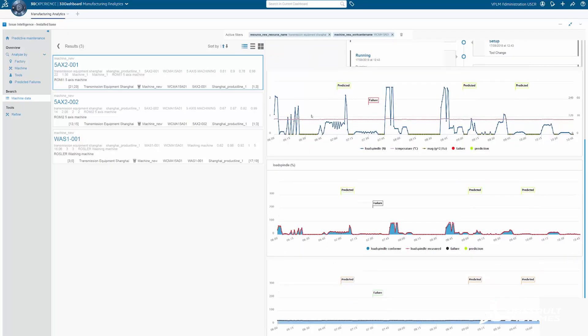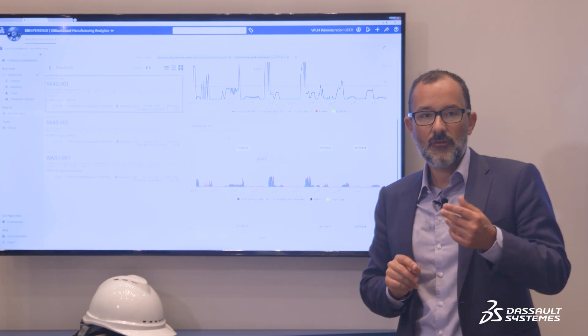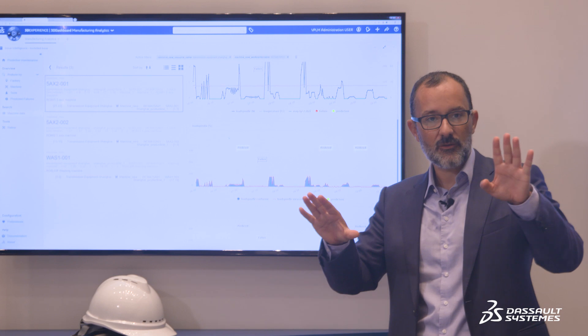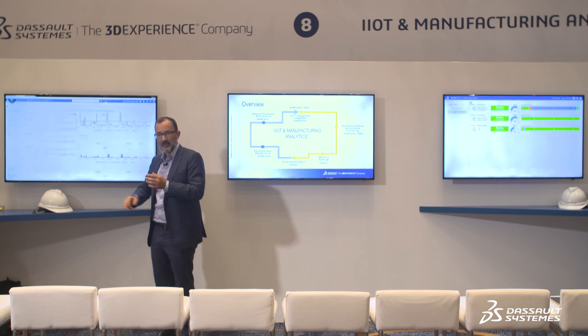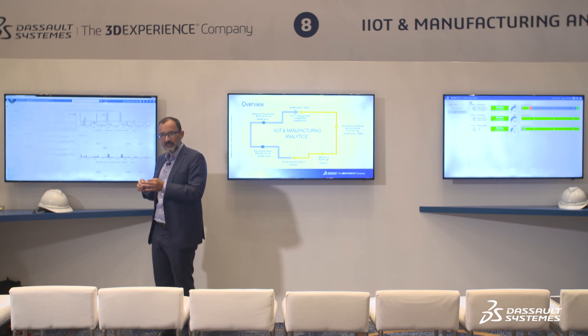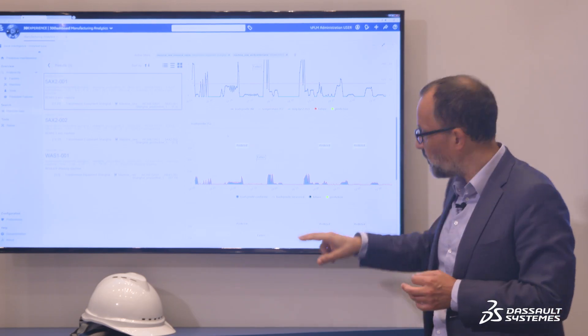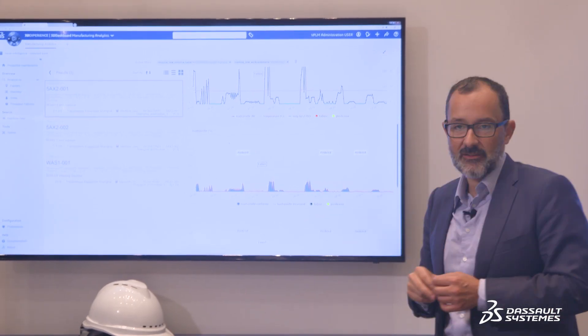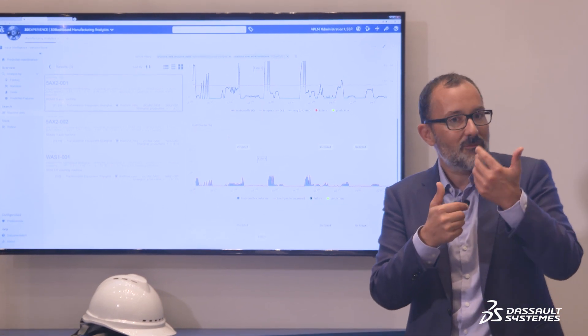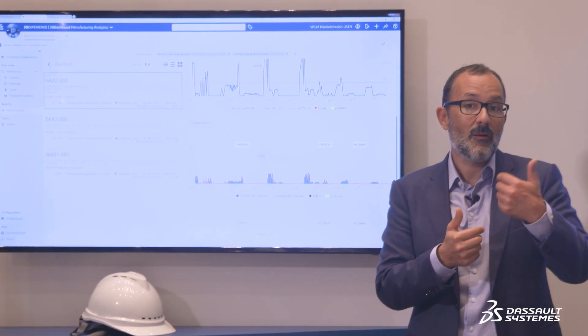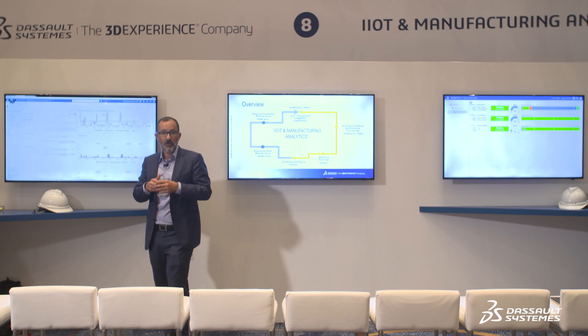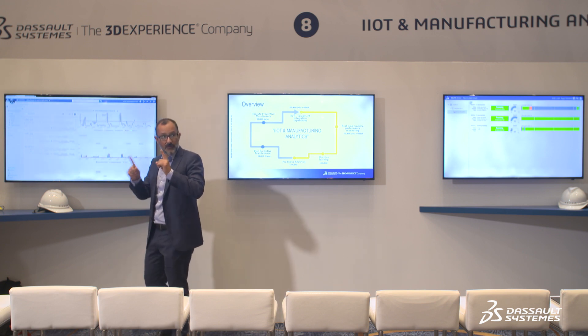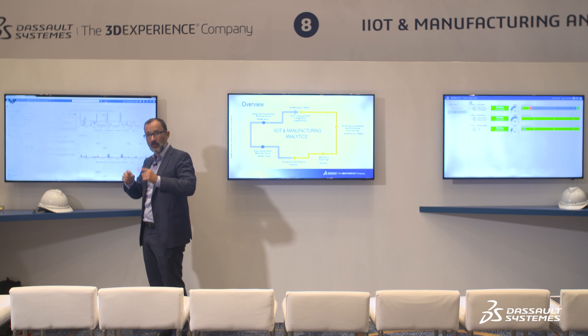More interestingly, what you see in blue here is simulated data. You've heard about the value of combining the virtual world and the real world — the blue is coming from the virtual world. We are running simulations of the load spindle, and comparing it with the red, which is the actual real value of the load spindle, so that we can identify deltas. These deltas alone would not be enough to suggest a failure, but they are additional triggers which, combined with all other data, allow us to identify risks for failures — a very interesting combination of virtual and real world.